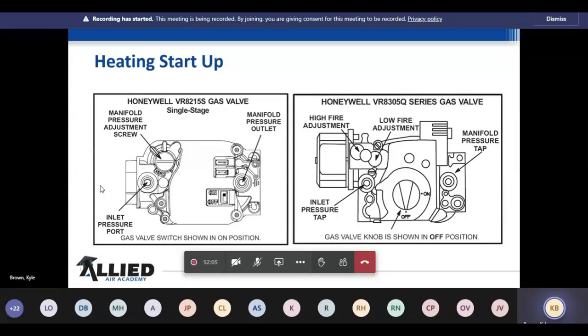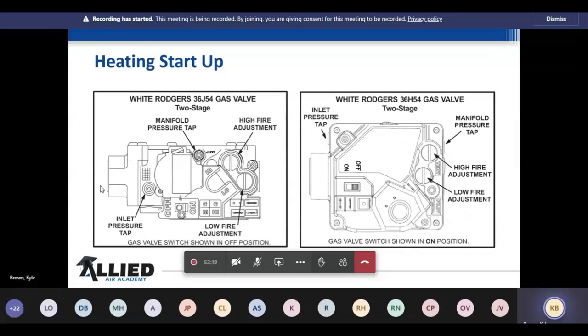And on the Honeywell valves, these are where you hook your manifold up to, and these are where you make your initial adjustments. Everything should be adjusted from the factory, but that doesn't mean we don't need to check it and then put it on a startup sheet. And these are the White Rodgers valves that we use as well. Same thing here. We really want to check and make sure, but we only use White Rodgers 2-stage valves. The only single stage valve we use is going to be a Honeywell.